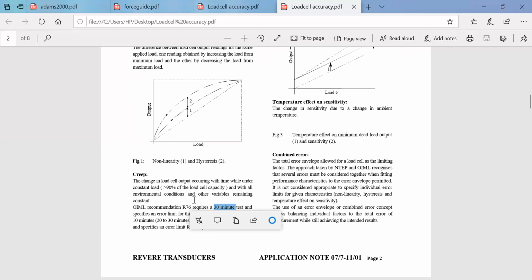In our experiment load cell, what we did was just add weight - 1 kg, 2 kg, 3 kg up until 10 kg - and we just took the readings. We didn't see what happens if you keep the same weight for a particular dwell time. Only then can you know the error deviation, the limit of error - the minimum error and maximum error it can show - and find out the deviation, the error bar for that particular load being applied. So that helps in defining how accurate the load cell we are using exactly is.